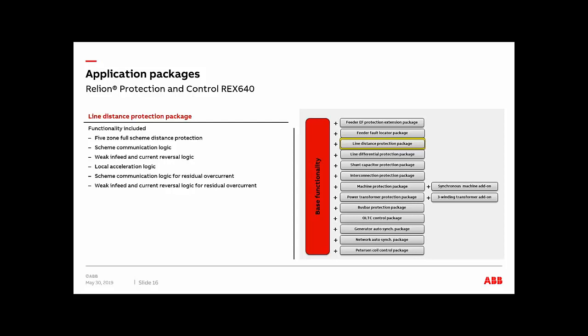Now, when it comes to the characteristics for the line protection that are supported, it's important to mention here that the relay has quadrilateral characteristic, Mho or circular, and something called bullet as well, which is a quadrilateral and the Mho characteristic combined. So it supports all of those forms of line distance protection.